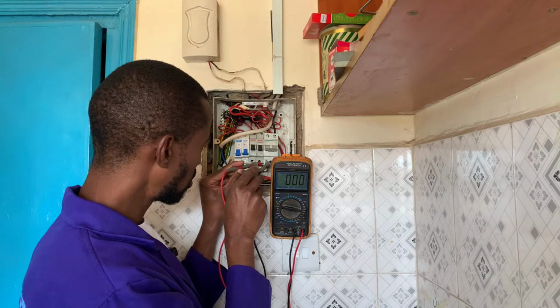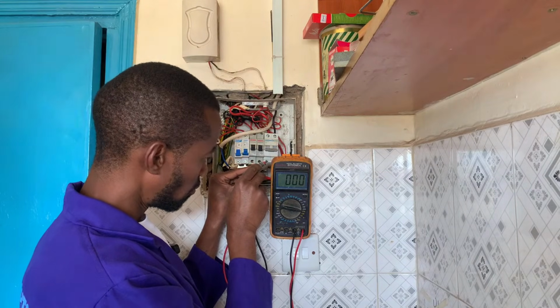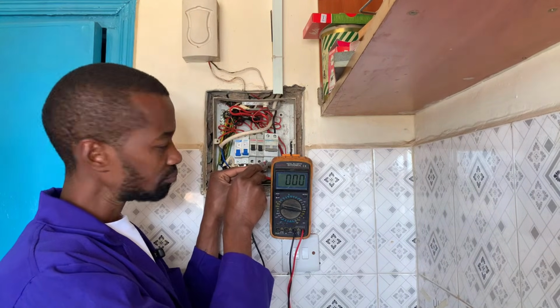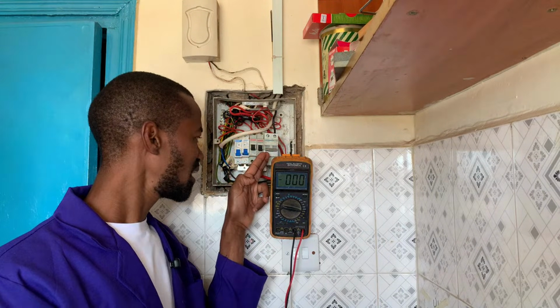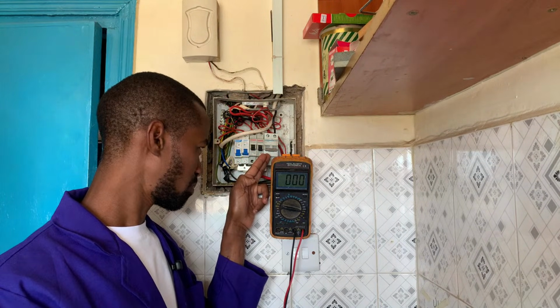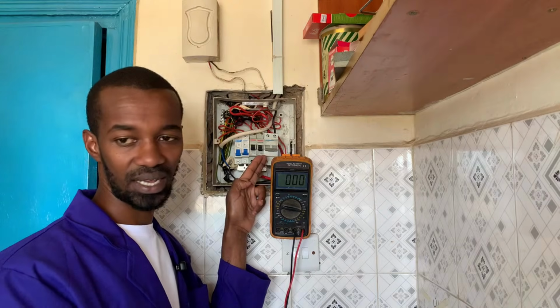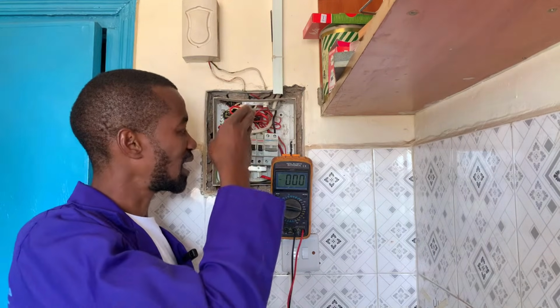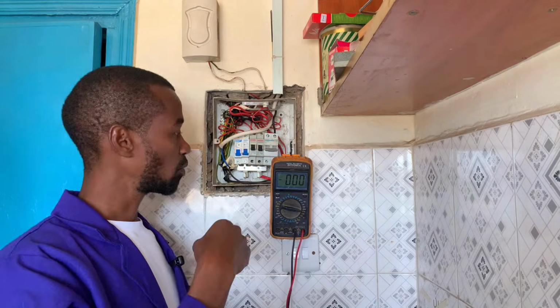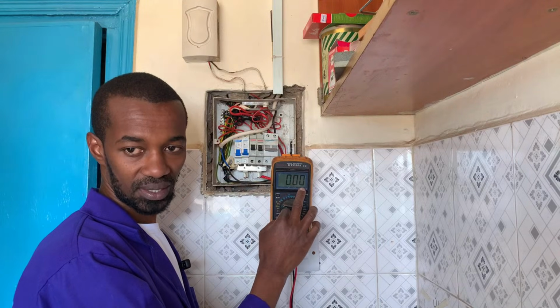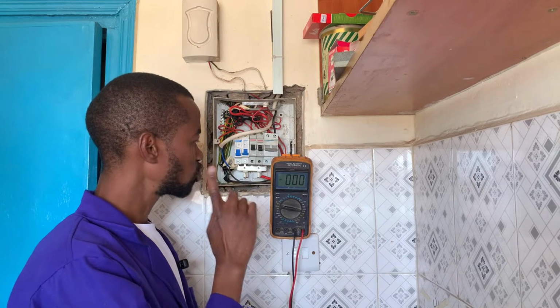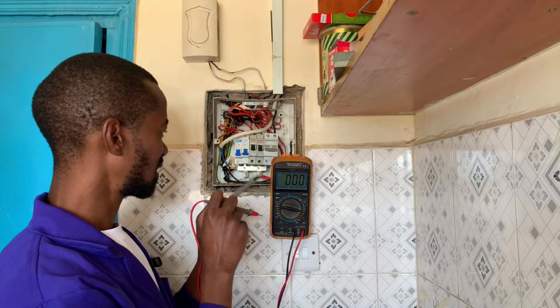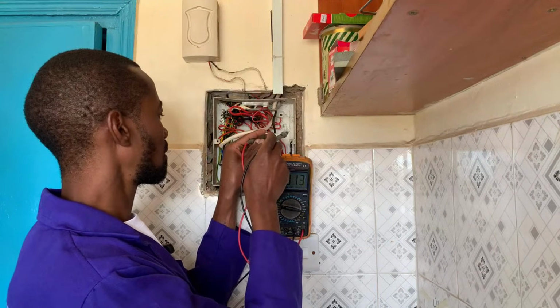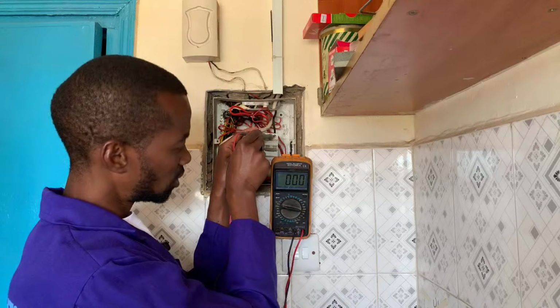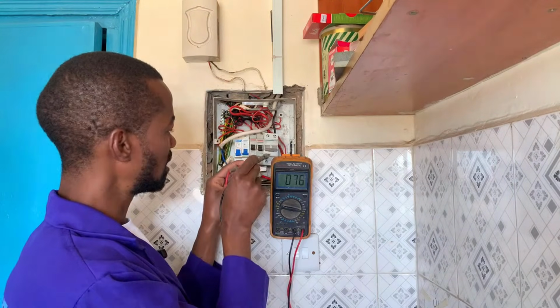On the output, as long as it is off, we are still getting zero. Now, assuming this DP-MCB, double pole miniature circuit breaker, had an issue and was allowing some voltage through, we would be getting some values here. So that tells us it is not bad at all in that scope of measurement.